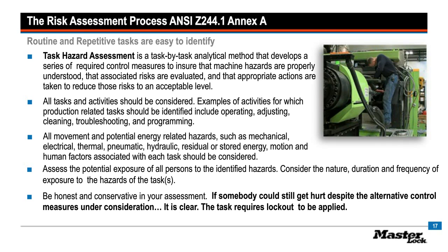Bottom line is you should assess potential exposure of all people involved in the task, including those affected by the job, consider the nature, duration, and frequency of exposure, and then develop measures that will protect those in the line of fire, as well as those that may be within the area that could be affected by a sudden startup.